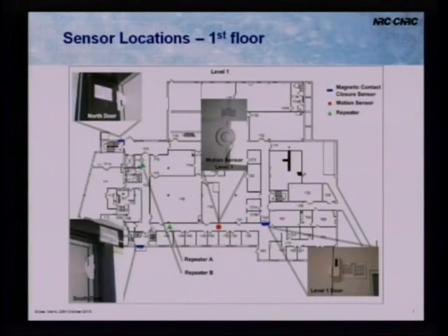I don't really want to go into too much detail, but just to show you some of the issues that we have with wireless sensors and getting them up and running within a building, because each building is unique. There's no one-size-fits-all solution. And because our building was unique, we had a lot of lab spaces, large metal boxes for ventilation research. And without knowing those were in there, it took a while to get the system working.